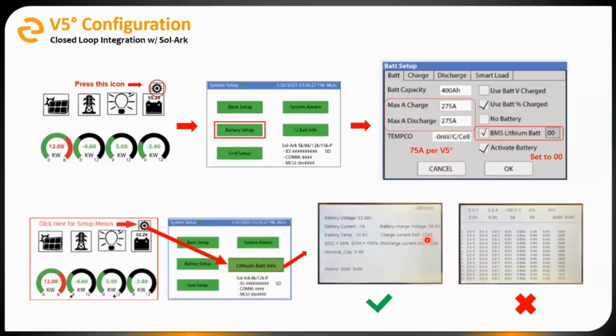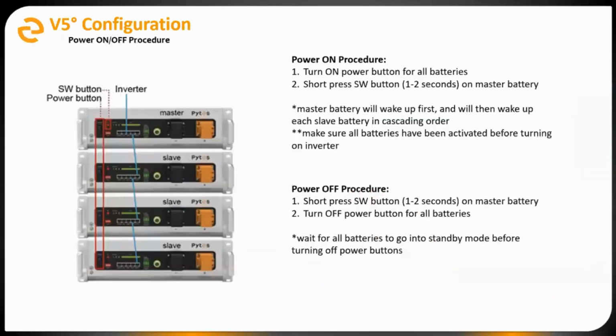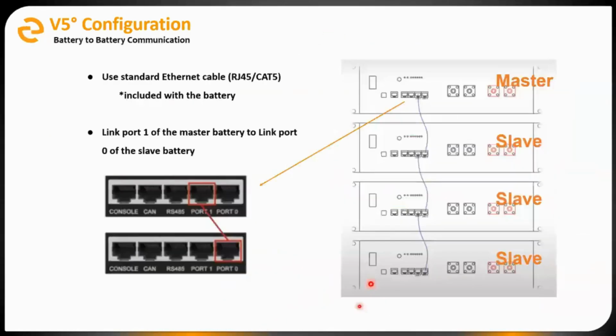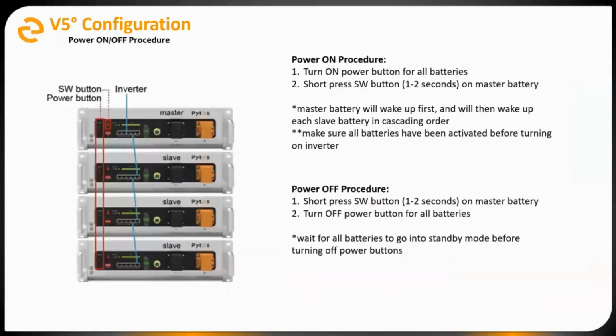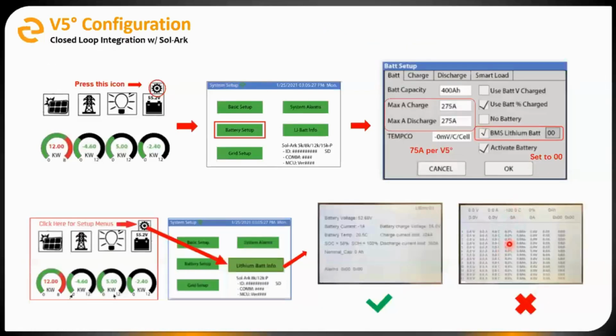So if you put in a 2 battery system and one of these numbers is 75 amps, that means maybe the system isn't seeing both of the batteries. We should see 150 for a 2 battery system. If you click this lithium BAT info button and you see this screen, that means something isn't correct. So this means that there's no communication between the Sol-Ark and the batteries. And at that point, now you can go through and try some of these things or make sure that those previous steps have all been done correctly.